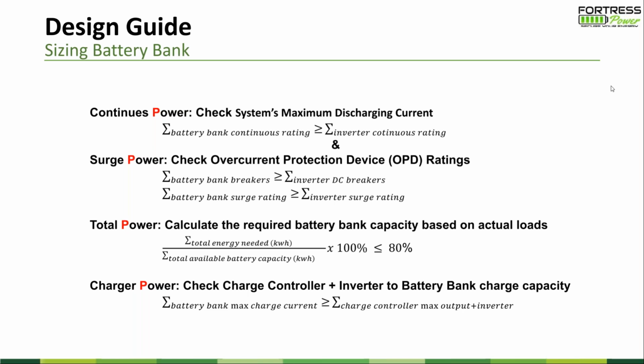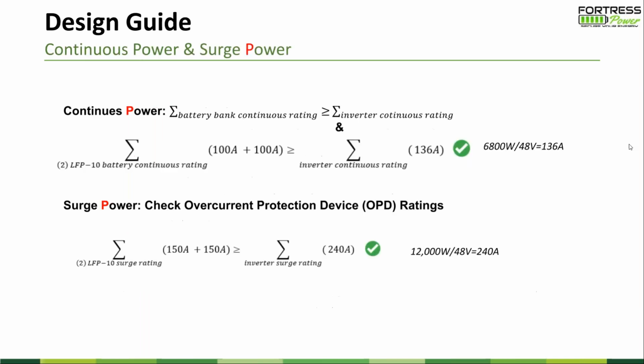We're going to look at the first tool first - let's look at continuous power and surge power. In this real case, we want the battery bank continuous power to be over the inverter continuous power rating. What happens is we don't want the inverter to pull too much power from the battery bank beyond the capability of the battery. Lithium is different from lead acid, but no matter which battery, you need to treat them fairly - if you put too much load on them, they die early. Especially with lithium, it has certain protection - a BMS system - so it will cut you off right in the middle of the night or when you use high power.